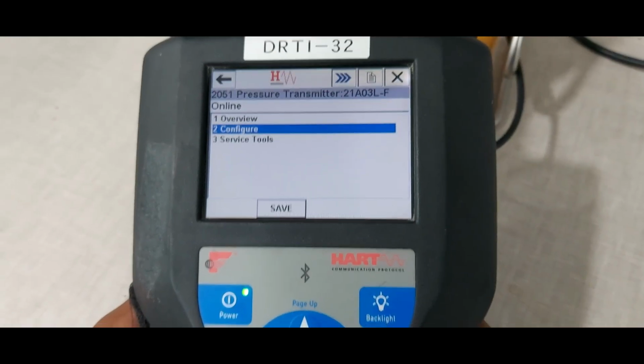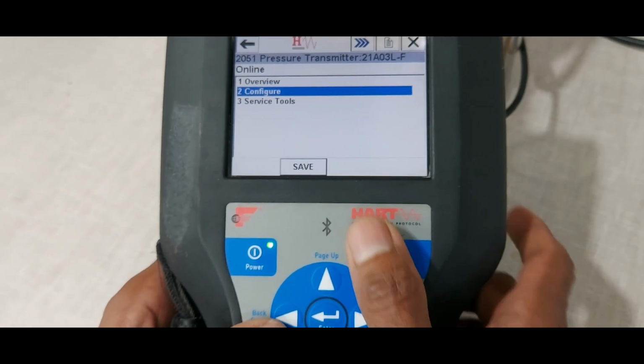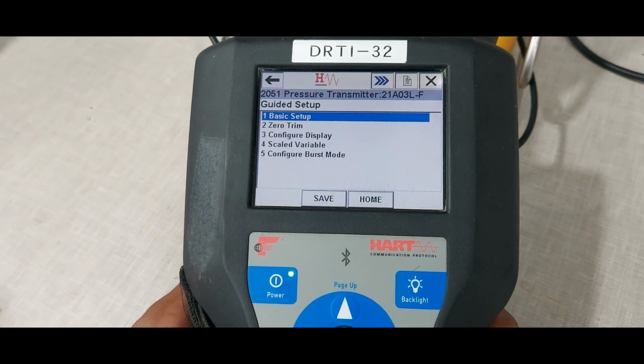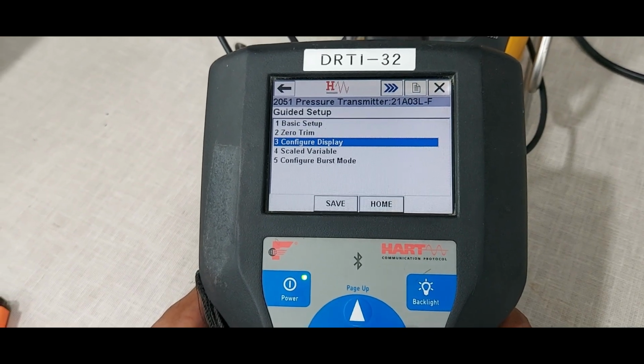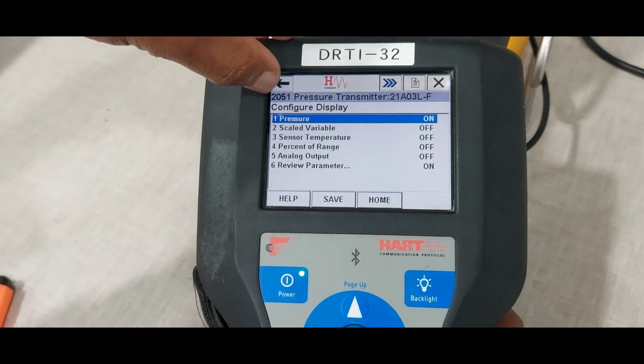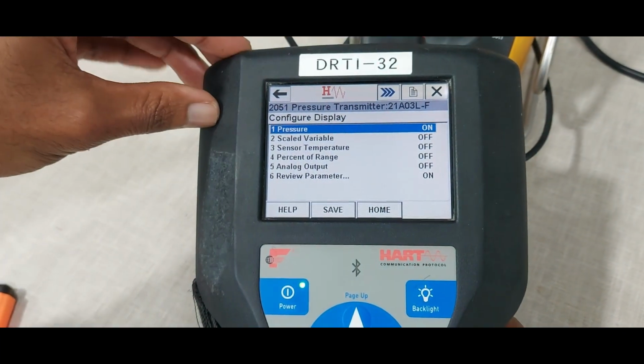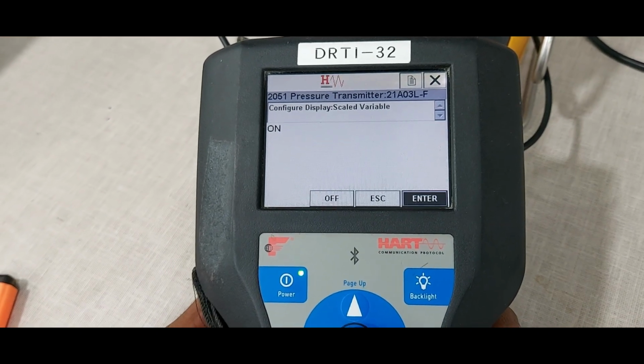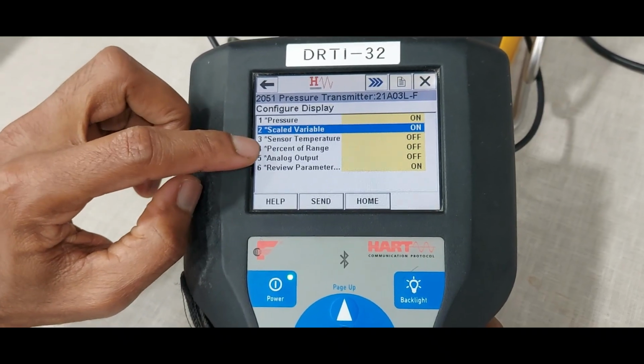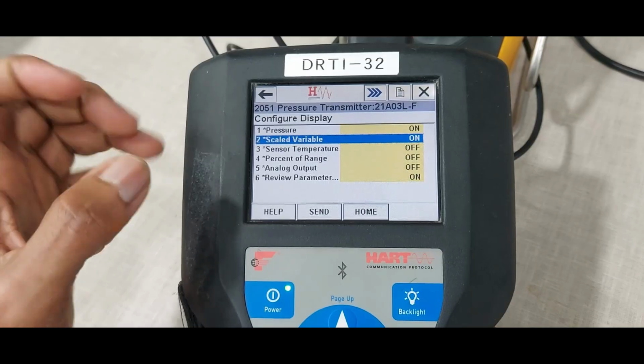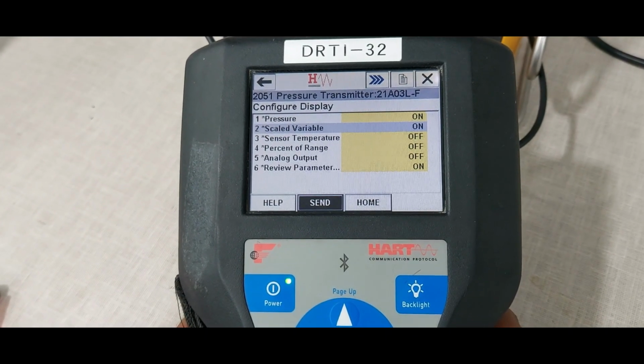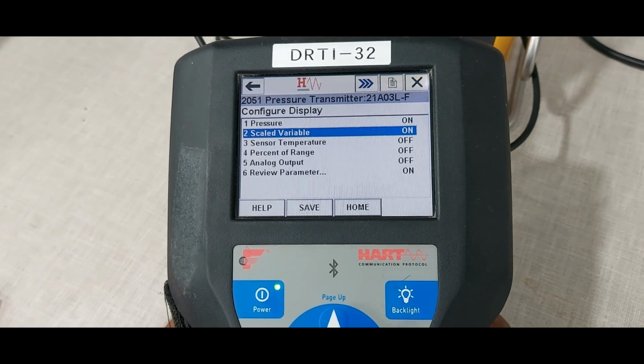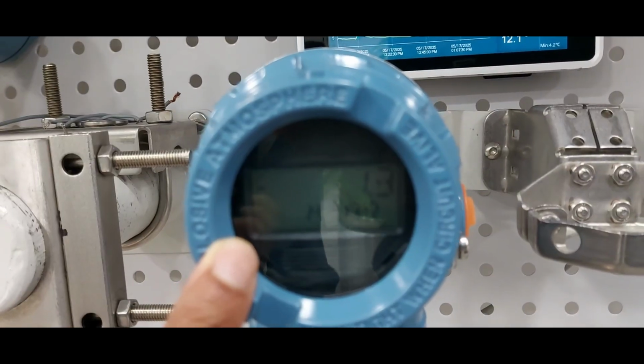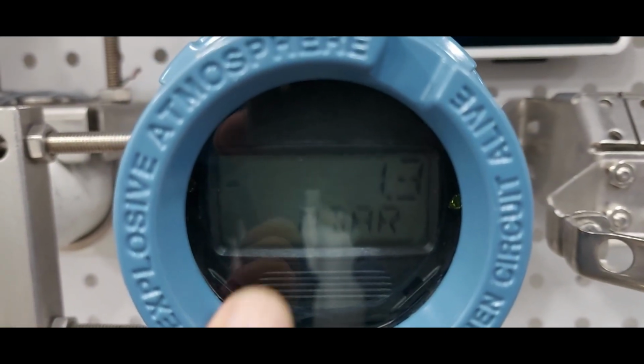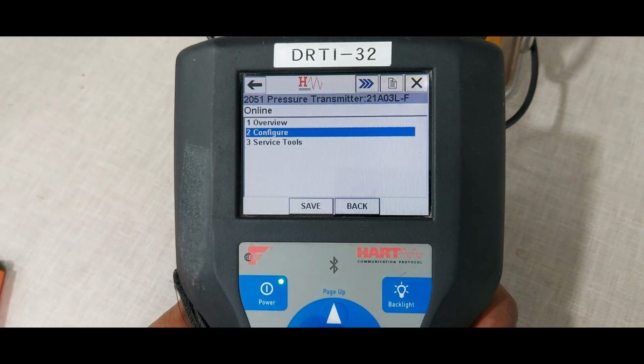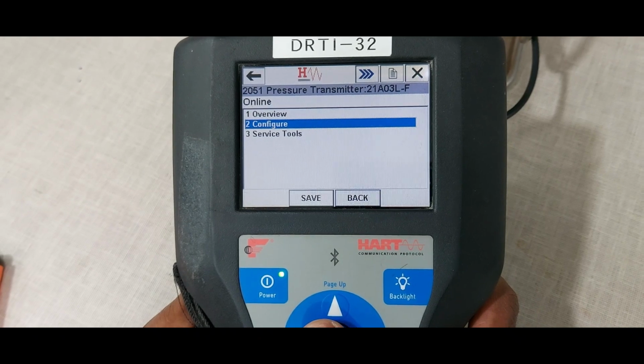Next we are doing the display setting procedure. Select the configuration menu and guided setup. Configuration of display, third one, and the pressure is already enabled. Scale variable is off condition. First, next we are selecting the on, and enter. Okay, temperature is not required, percentage also not required, analog output also not required, review parameters is required. Okay, next select send. Now display is showing both conditions, dp value and flow value. Okay, display configuration is completed.